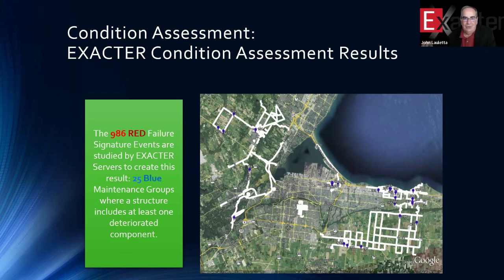efficacy in the results. So throughout our history as a company, almost 18 years, we've kept a KPI internally that is when we say there's a problem, do we find a problem? And that efficacy is higher than 99.5%. So we've managed to, through years of study, research, and development, optimize our algorithms to the point where we tell you there's a problem, go fix it. And you'll eliminate either a pole fire or a potential circuit outage that can be predictively eliminated.